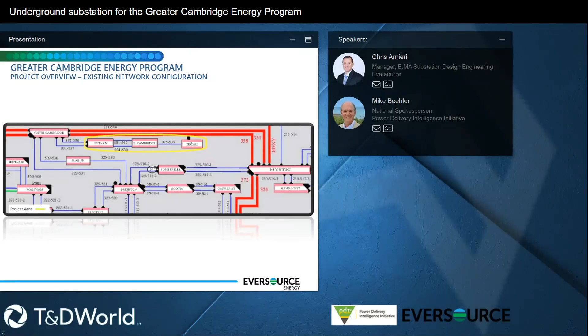The proposed solution was to add a new substation, which we're calling 8025, a below-grade substation, and reconfigure it to bring 8 transmission lines, all at 115,000 volts, into the substation with proper connection, so it's no longer a radial-fed substation. The substation consists of 115,000 volt switchgear in a 6-bay breaker and a half arrangement, with 8 transmission lines and 4 oil-filled power transformers to serve the increased distribution load, as well as electrification of the area, including EV charging.